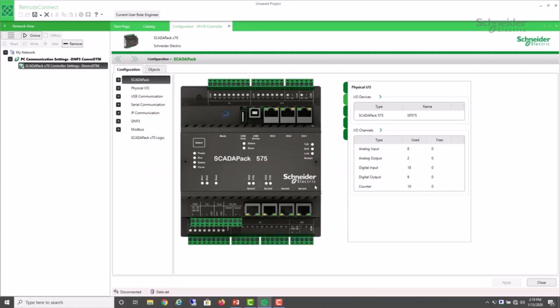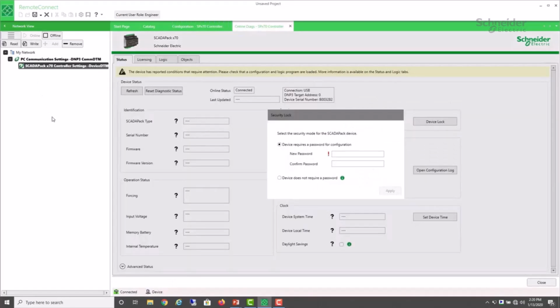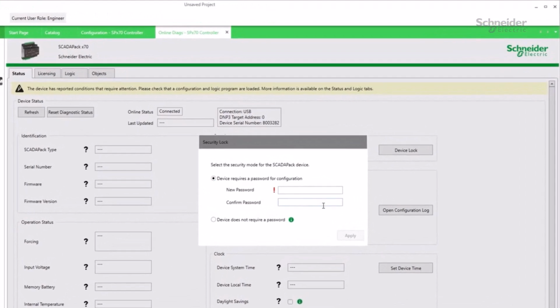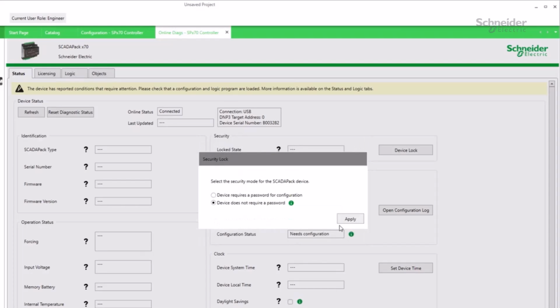I have a new SCADAPack 575 connected to my updated RemoteConnect. I have version 3.6.3. I'm connected over a USB cable, and I'm going to select Online. And here it is. I have a new SCADAPack, so it does arrive locked. If I don't see this dialog and I am indeed connected, the status says connected, then I'll need to perform a cold boot of the controller to reinitialize controller security in order to see this dialog. So to disable device locking, I select the second bullet, a device does not require a password, and apply.